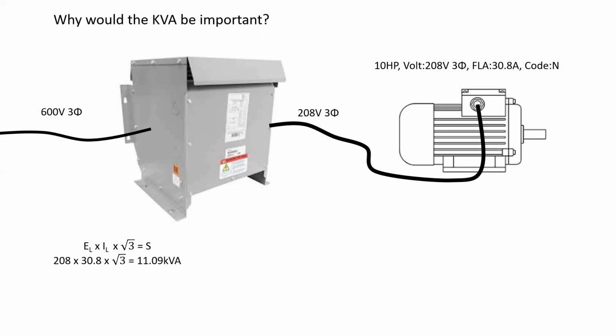But remember, that FLA listed on the nameplate is only the current that the motor will draw when driving its rated load. What this will result in is a severely undersized transformer. The transformer will not have enough capacity to allow the motor to start because the motor will have a significant inrush of current when it is first turned on.